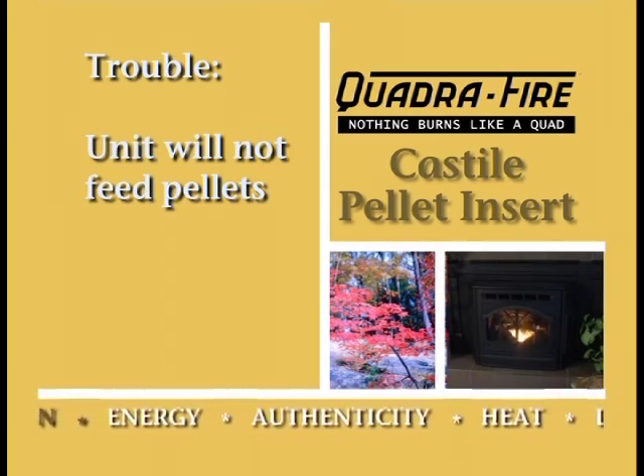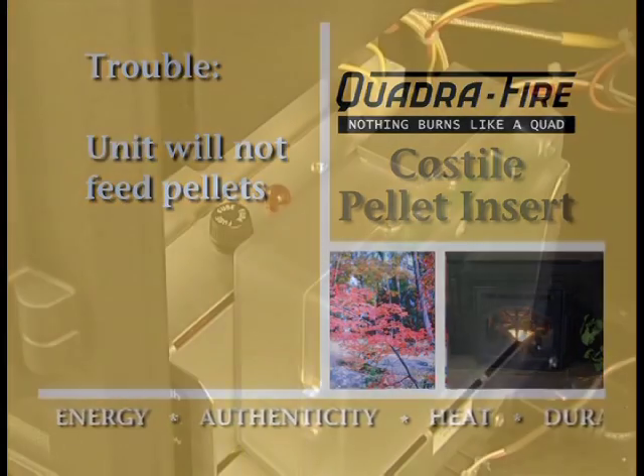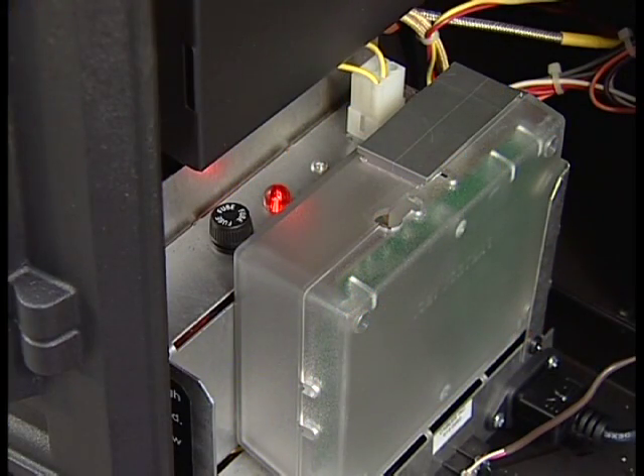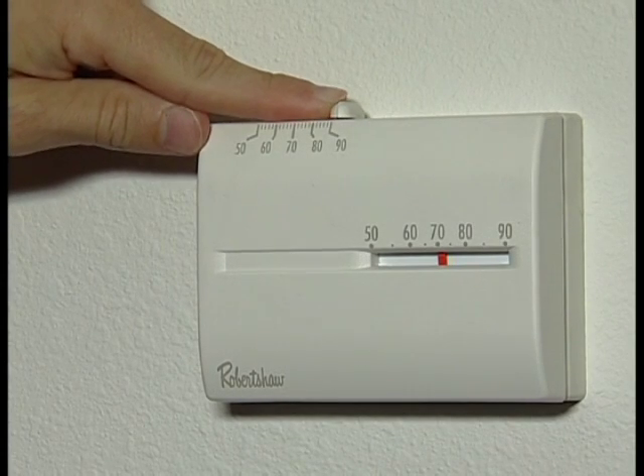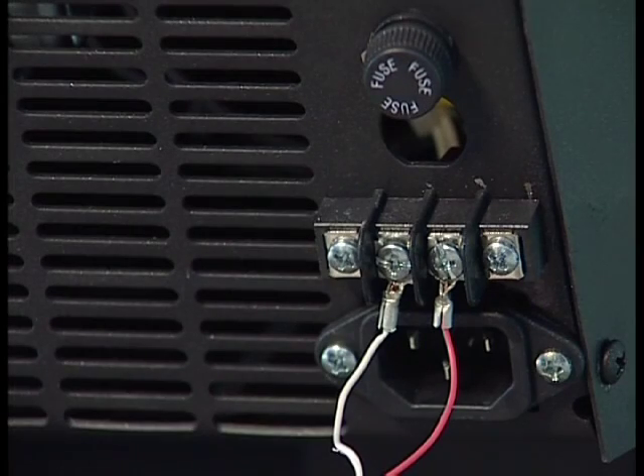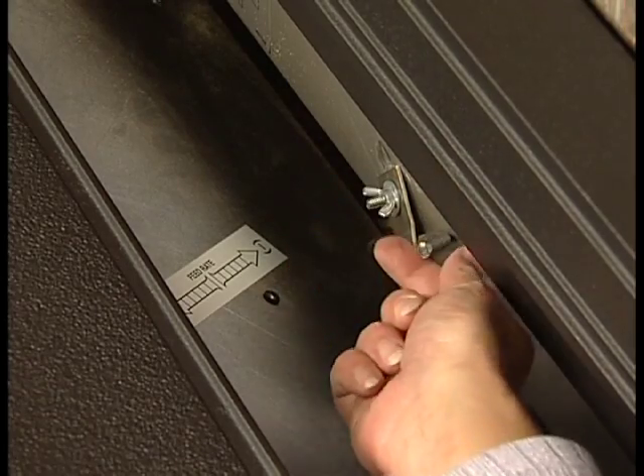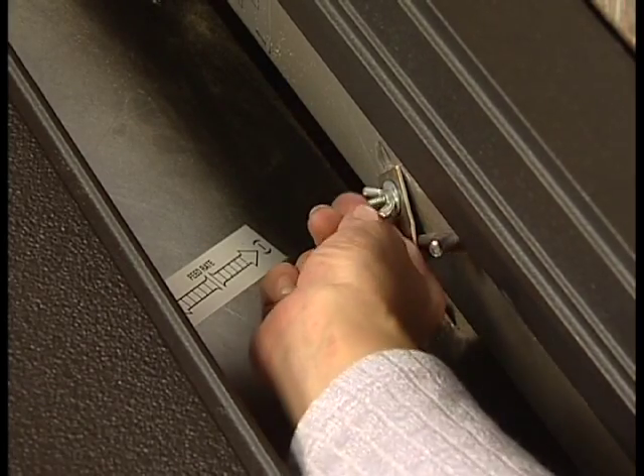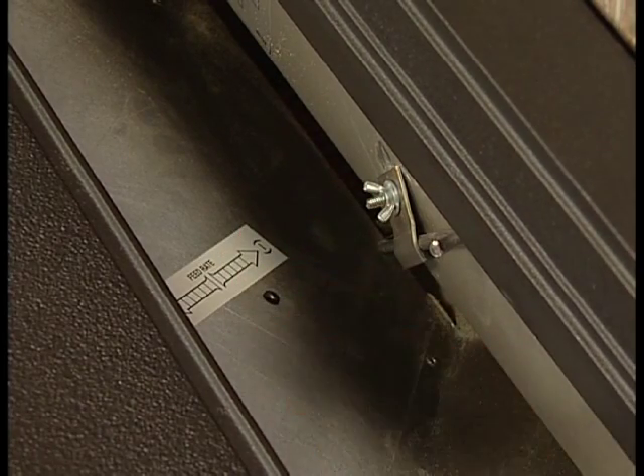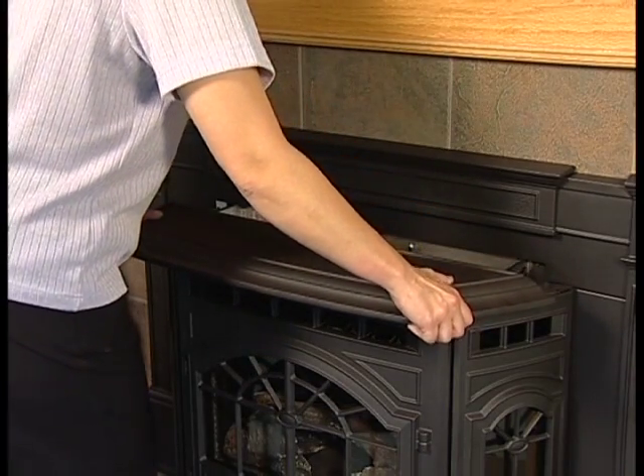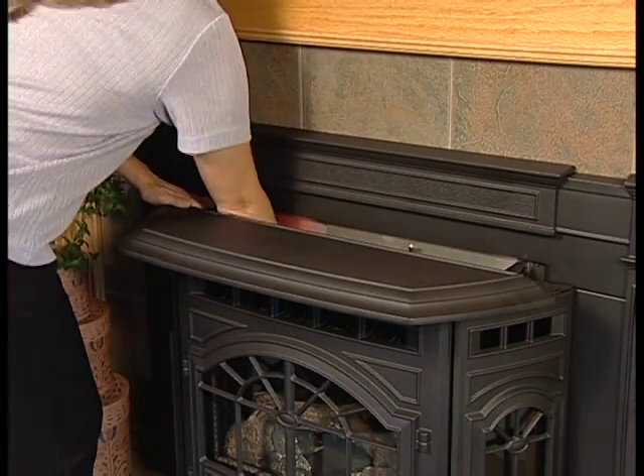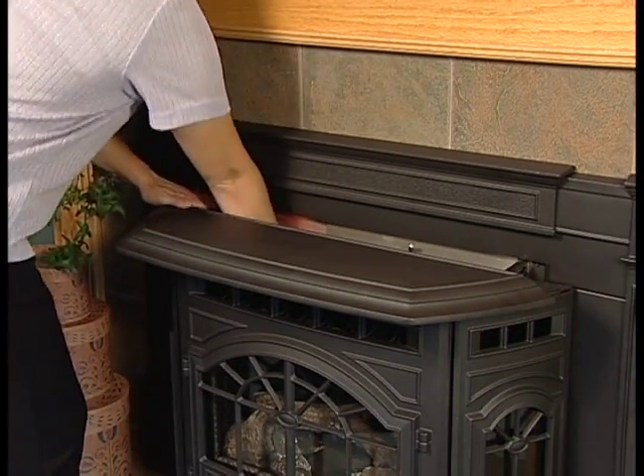The unit will not feed pellets. Check the call light on the stove and make sure it's on. If the call light is not on, check the thermostat and thermostat wires. Check the feed adjustment plate in the hopper. If the plate is closed too far, pellets will bridge over the fuel opening in the hopper and the feed tube will empty. To clear this condition, jab your hand several times into the hopper.